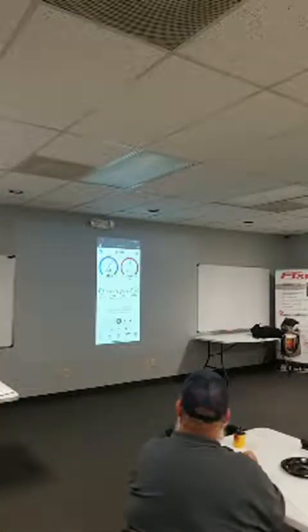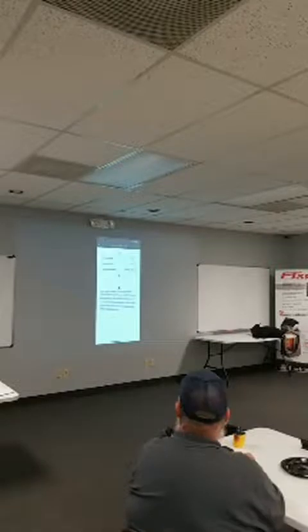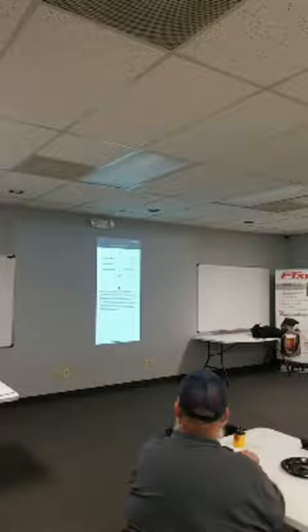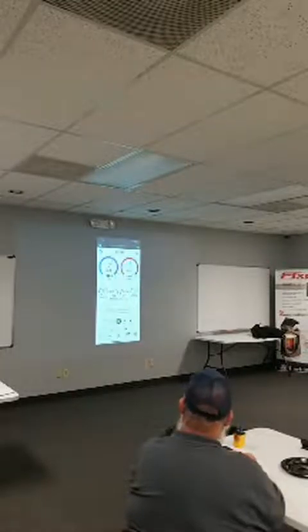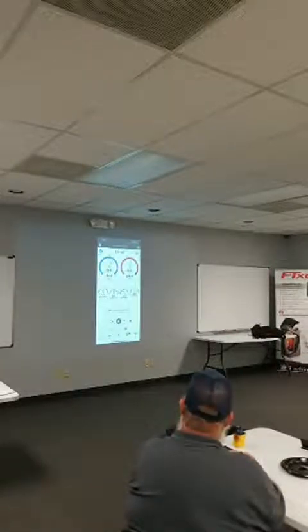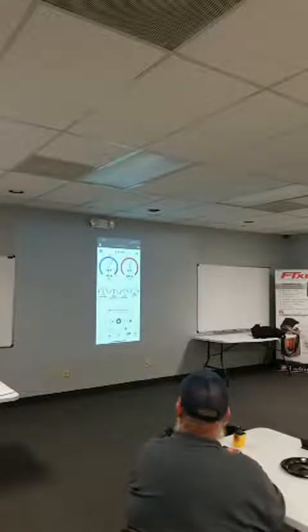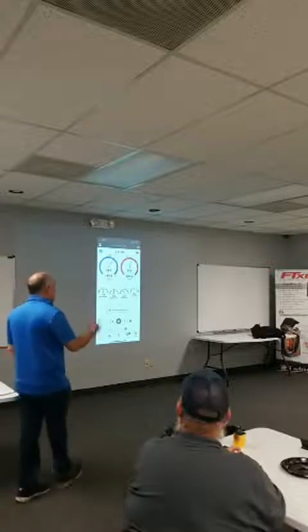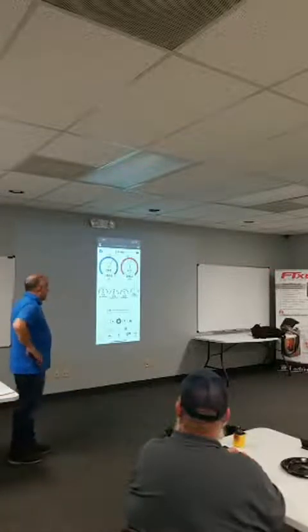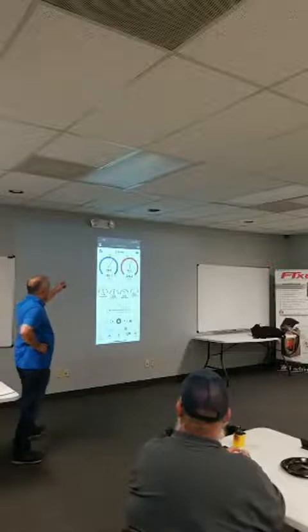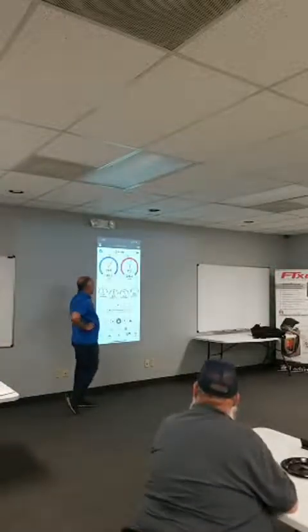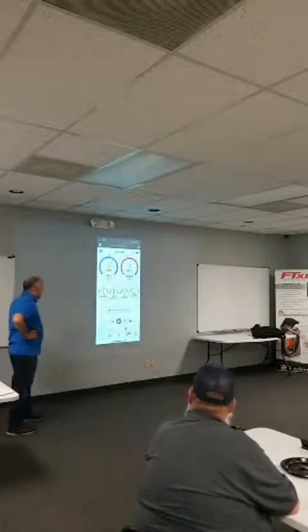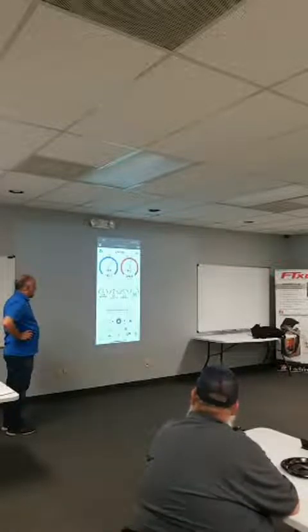So when you tap on this gauge right here, it's going to tell you the allowable range is 70 to 85. What happens above 85 degrees? We're just too far out of design for the system to work right. So there's absolutely a range for anything on this system, right? Supply dry bulb, why is that? Are you in the supply? Seems like maybe you got the outdoor air and supply probe mixed up too. Yeah, I could have that. Yeah, and that's why we're outside the range. It's all garbage in, garbage out, so flip those two.